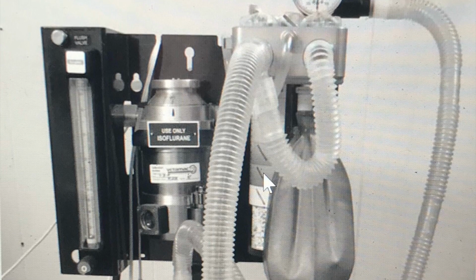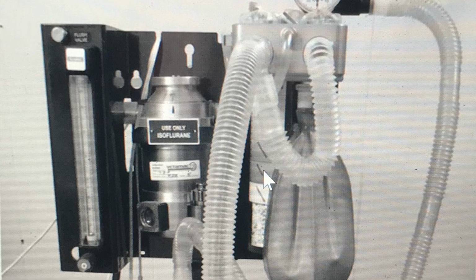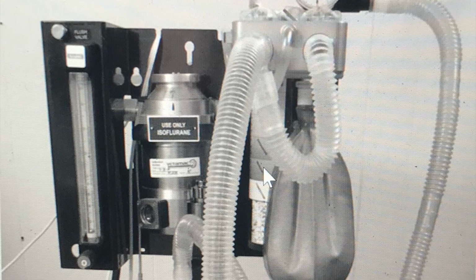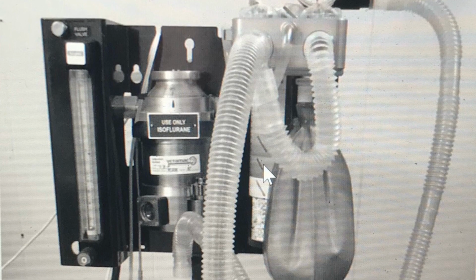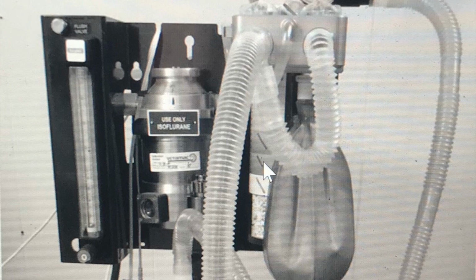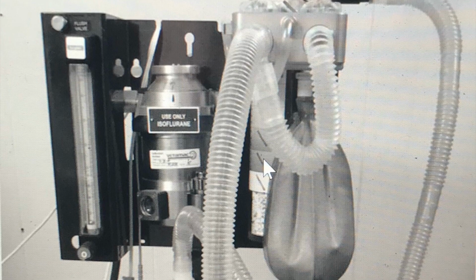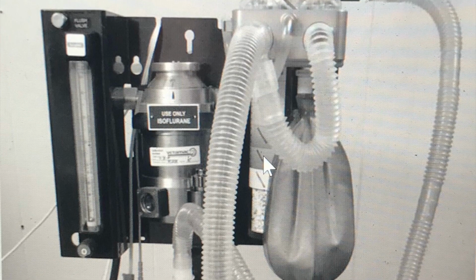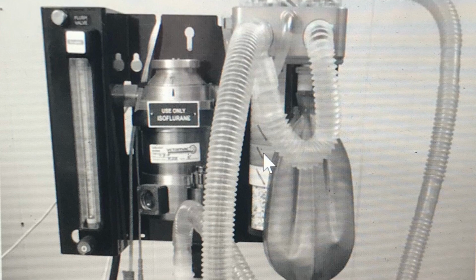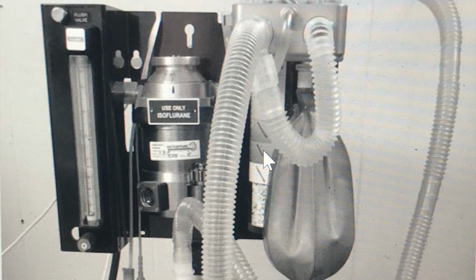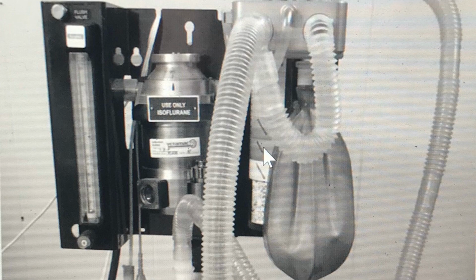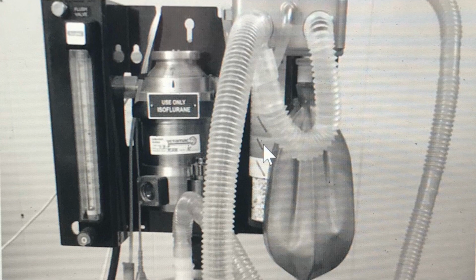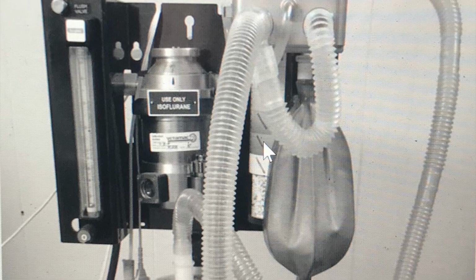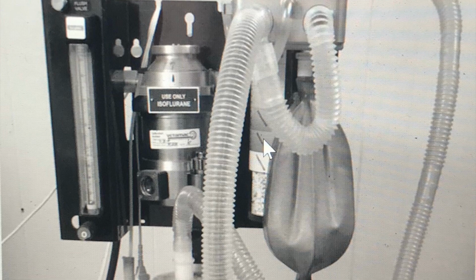Then you'll go and check the flow meter. You will turn the flow meter to about 1.5 liters per minute. Verify that this is staying stable and not moving up or down. Then you will turn off the flow meter and the ball should return to 0. Do not use the machine if the flow meter does not function right. At this point, you will check your vaporizer to make sure that it has adequate liquid level. If not, you will fill it with the correct liquid as necessary and tighten the cap.